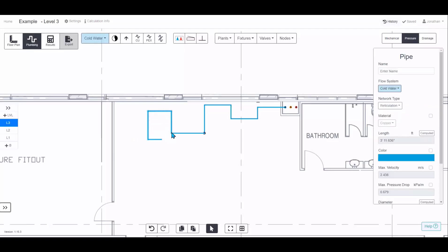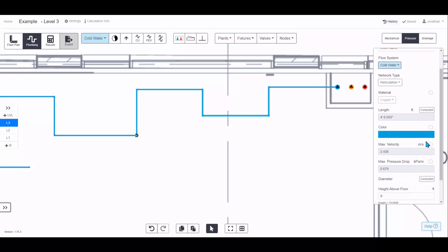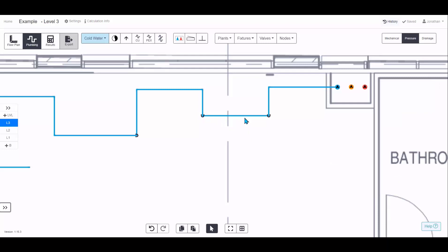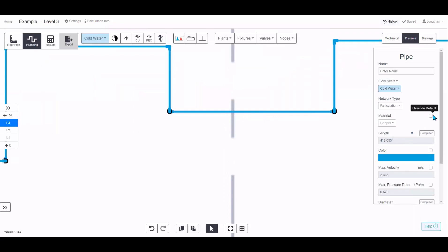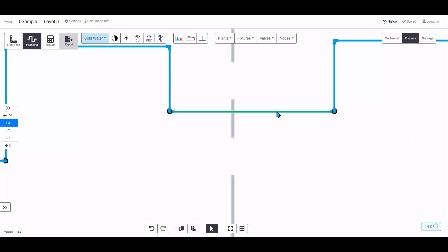You can easily move pipes around. To change the height after drawing, update the value in the properties — semicircles will appear to indicate the change. If a section of pipe needs to be overridden — say it's an existing stainless steel pipe at a specific diameter — override it, and it will highlight yellow so anyone reviewing the design knows something is different.